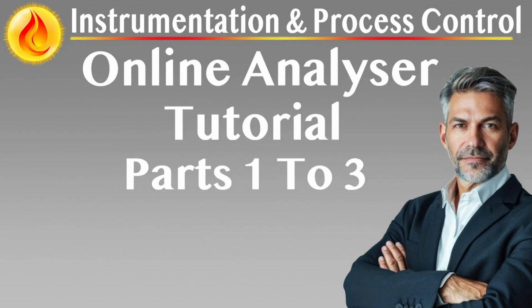Compliance with international standards. All analyzer systems and associated equipment must comply with relevant international codes and standards, including the IEC 60079 series for electrical equipment in explosive atmospheres, IEC 61010-1 for safety requirements of electrical measurement equipment, IEC 61285 for safety of analyzer installations, IEC 60079-2 for artificial ventilation of analyzer enclosures, API 555 for process analyzer systems design guidelines, and API 505 for area classification and ventilation practices in hydrocarbon facilities.